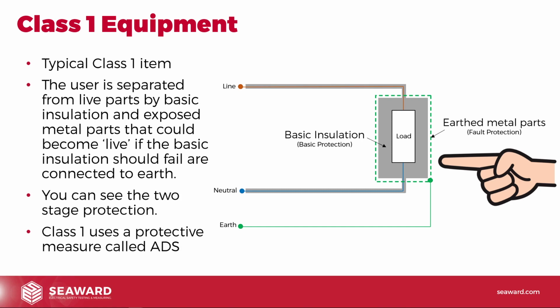A typical example of this might be an office fan. The guard around the fan blades is metal. It's exposed so you could touch it, but it can't become live under fault conditions because the live parts are in the motor. If the insulation within the motor was to fail, the body of the motor is earthed, so that will automatically trip off and automatically protect the user. The guard around the outside of the fan is really just there to stop you poking your finger in. It's not there to provide electric shock protection. It's not going to become live in the case of a fault.